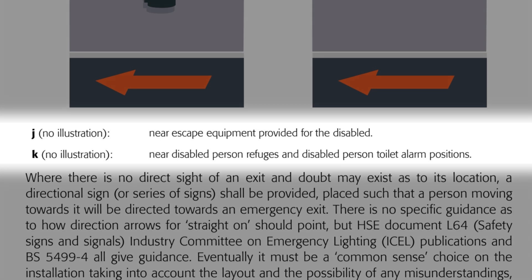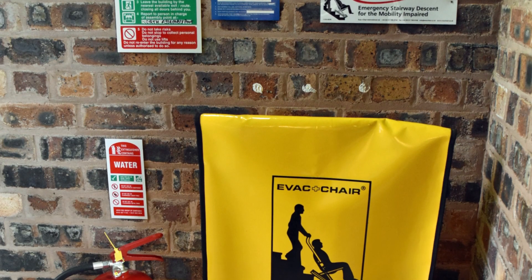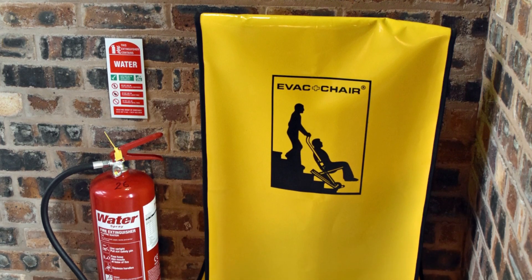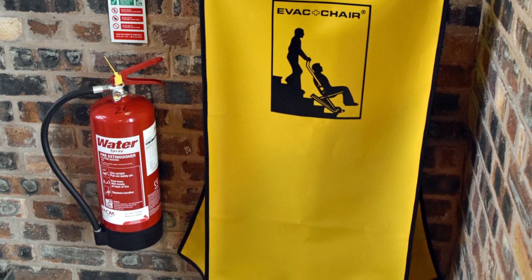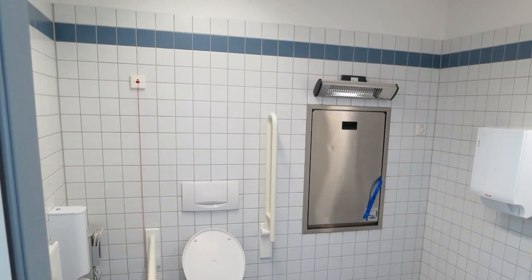There are also examples without illustrations: near escape equipment provided for the disabled, and near disabled person refuges and disabled person toilet alarm positions. This might include stretchers for manually carrying people downstairs if they're in a wheelchair — in an emergency you're not supposed to use lifts. Refuge areas are usually at landings of stairwells designed to minimize fire risk, with two sets of fire-resistant doors and often a special intercom communicating with a central location. Accessible toilets also require toilet alarms, and all these items require emergency lighting near them.